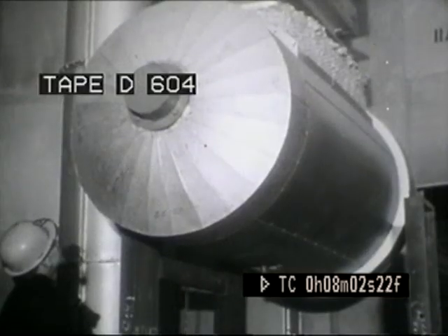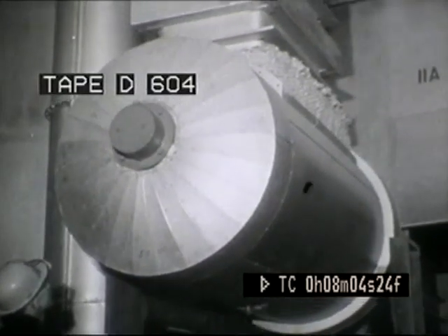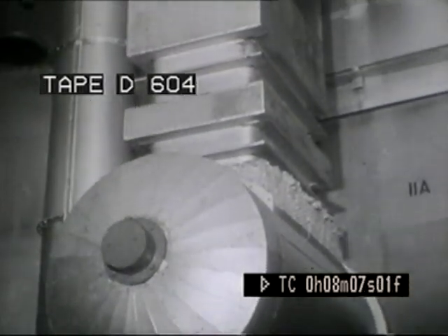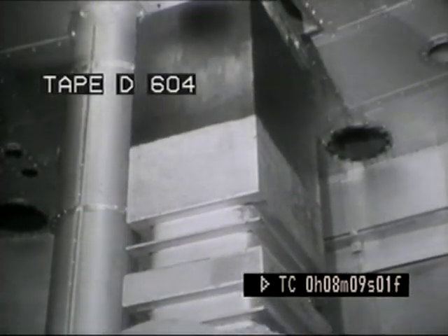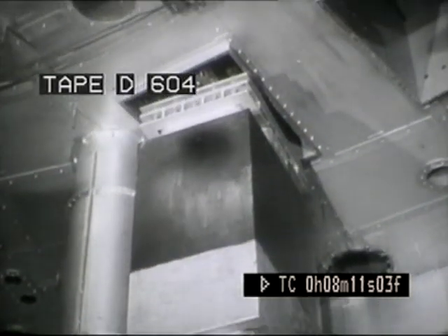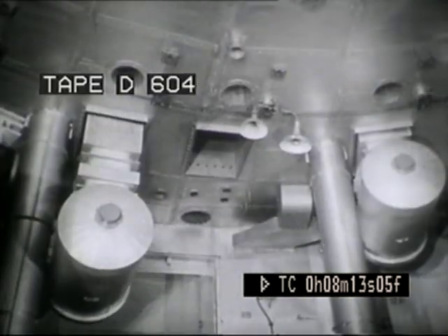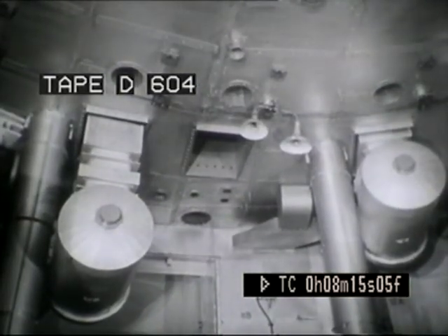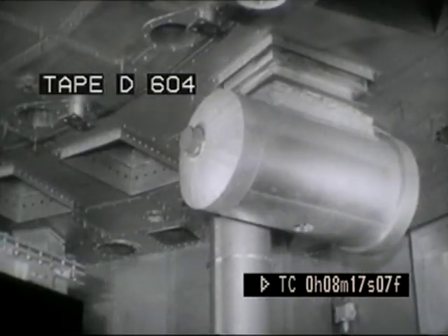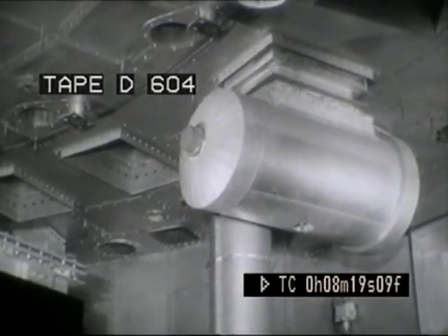These pumps will circulate the coolant through the reactor and primary heat exchangers. Conventional methods of pumping were unsuitable, but as the coolant was a liquid metal, electromagnetic pumps could be used with the advantage of no moving parts and therefore no driving shafts which would require sealing.